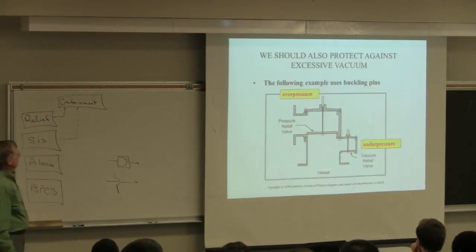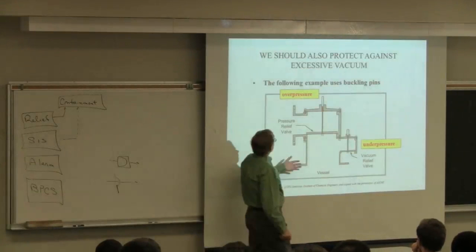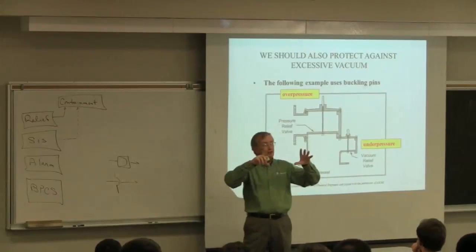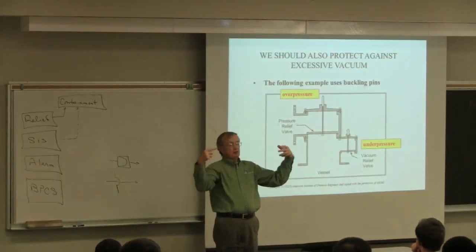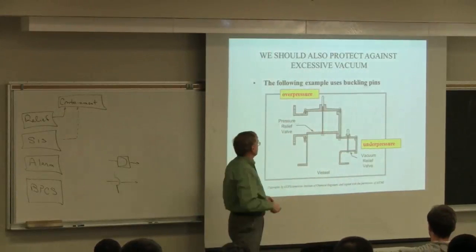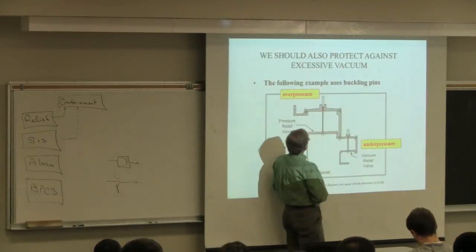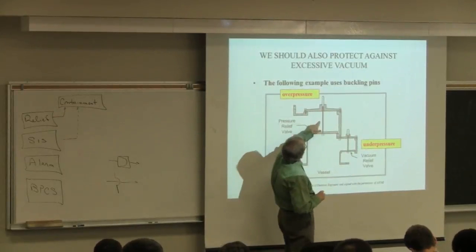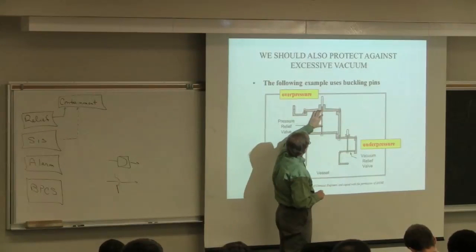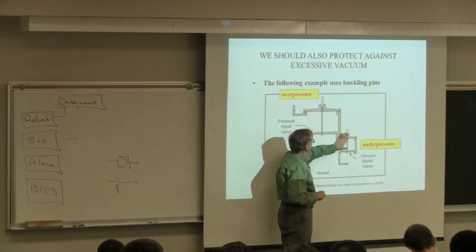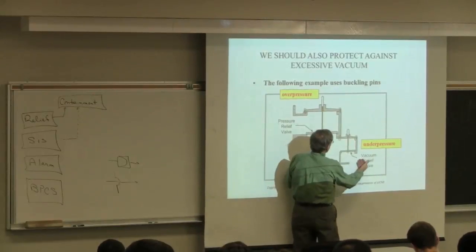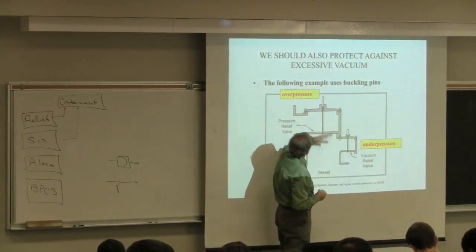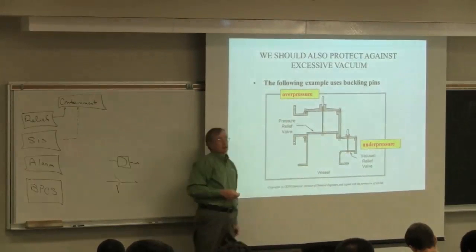Remember that for vessels, you can have both overpressure and underpressure hazards—like the penicillin reactor example where there was no protection against vacuum. There are also shear pin devices: these break at a certain force—if pressure is too low, the pin breaks and sucks air in; if too high, it breaks the other way and vents material.